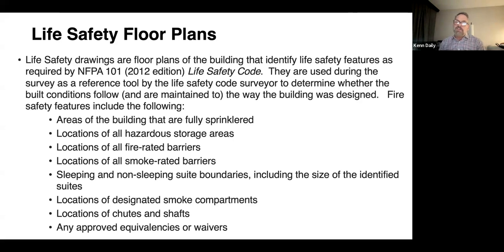One of the most critical aspects of this whole process would be making sure that you identified your fire walls and or your smoke walls in your building. As you know, surveyors will go to those barriers or those walls and then have you look above the drop ceiling typically to find your penetrations, which, as I showed you in Pennsylvania, is both leading citations. So you want to make sure those barriers are identified, and you have to make sure you know where they are. I've seen a number of questions by surveyors across the country asking, do you really know where your barriers are? Is this a smoke or fire barrier? In some cases, they're nothing.